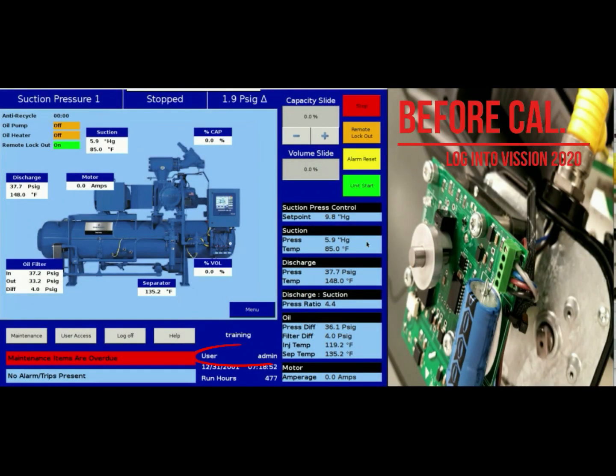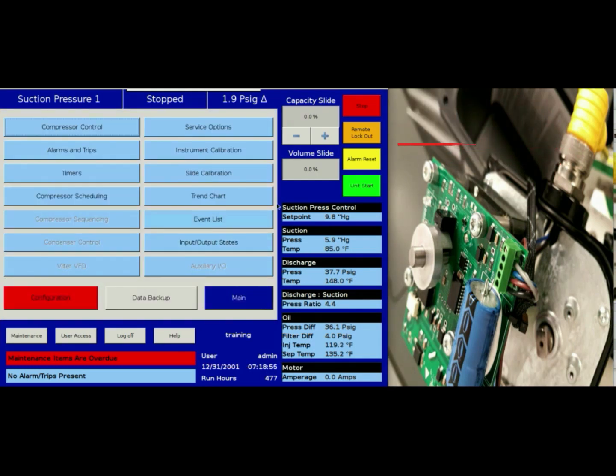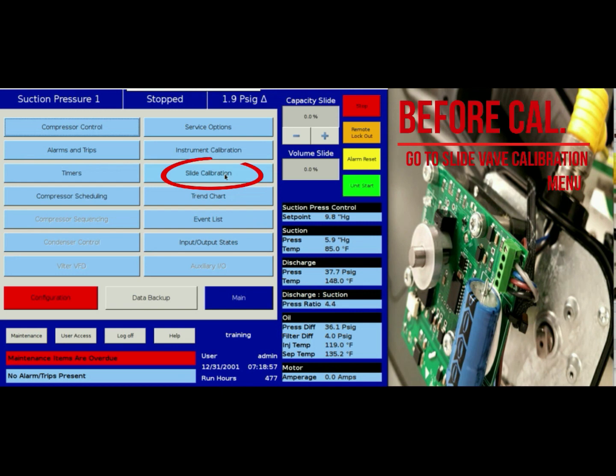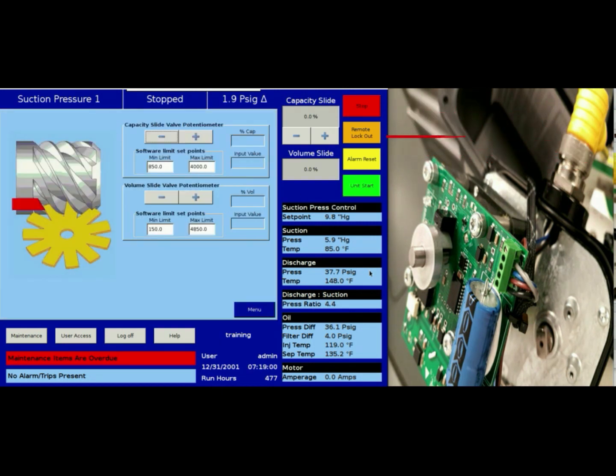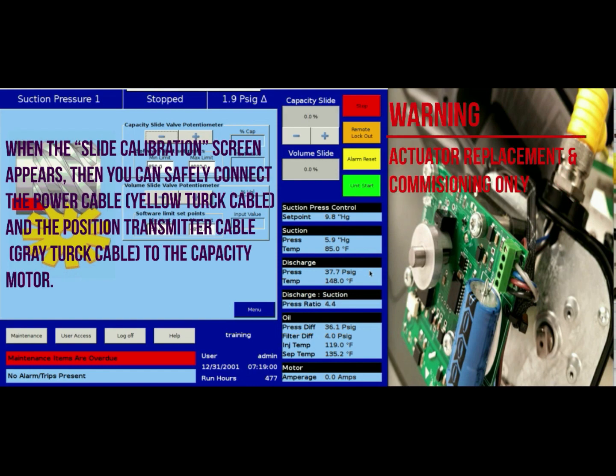Be sure to leave the power wires disconnected until you are in the slide valve calibration screen. This will prevent motor malfunction and command shaft damage. The power wire is the bigger connection on the bottom of the actuator.